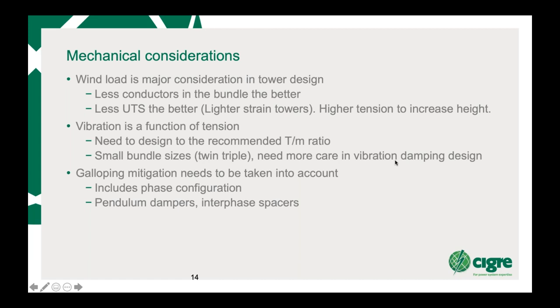The reason is that if you're looking at a spacer damper with many subconductors in the bundle, you'll find that the actual frame has a lot of inertia. So you can actually get a lot of energy out of the conductor into the spacer damper. But on twin and triple, it's very difficult to do that. So twin spacer dampers, in fact, are not very common.